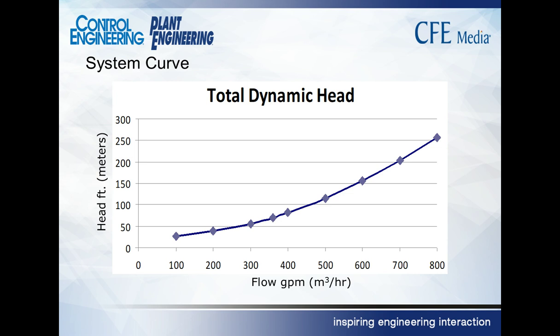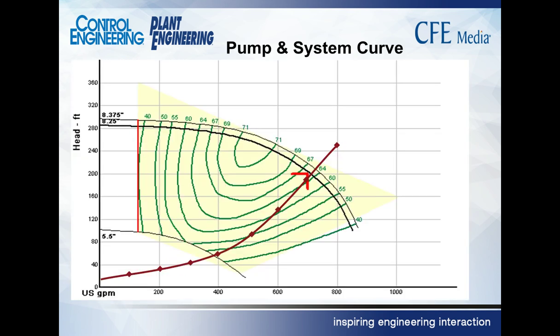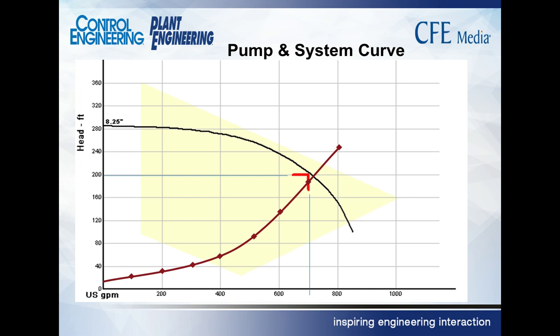So what are the axes on a system curve? The vertical axis is head. The horizontal axis is flow. Wait a minute. We had a pump curve that had the same vertical and horizontal axes. Why don't we just plot the pump curve and the system curve together, and the point of intersection is the operating point for that pump? Everybody see that the operating point is the intersection between the system curve and the pump curve.